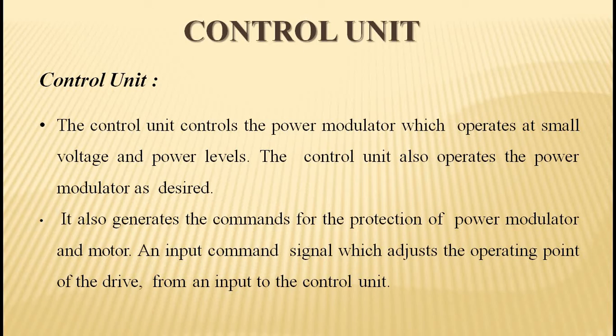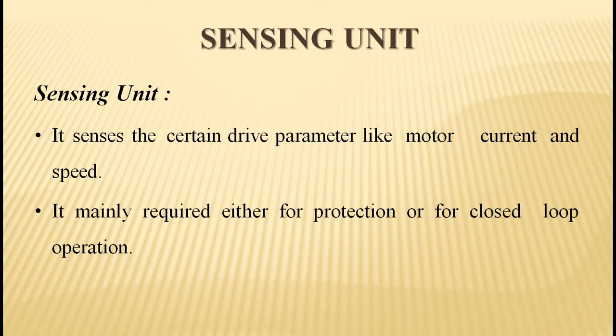The next component is the control unit. The control unit controls the power modulator, which operates at small voltage and power levels. The control unit also operates the power modulator as desired and generates commands for the protection of the power modulator and motor. An input command signal adjusts the operating point of the drive. Next is the sensing unit, which senses certain drive parameters like motor current and speed, required either for protection or for closed loop operation.